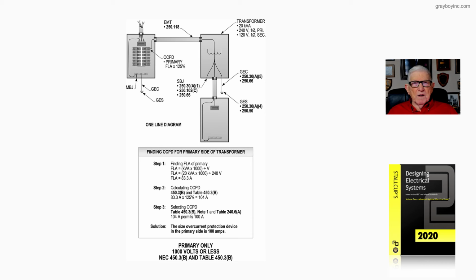And then again, you can place that 100 amp in a 100 amp disconnect, say, or a 100 amp circuit breaker, whichever. If you use a disconnect, that's 100 amp fuses. If it's a circuit breaker, a 100 amp circuit breaker. So the solution basically says the overcurrent protection device in the primary side of that transformer should be rated at 100 amps by the solution by rounding it down.